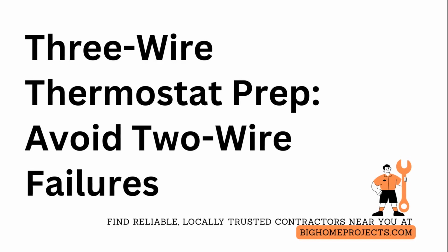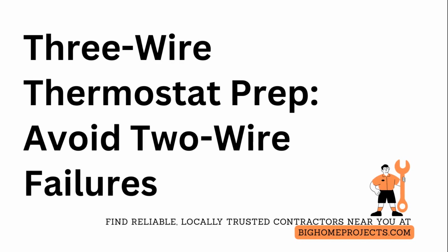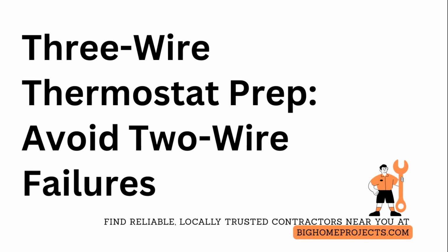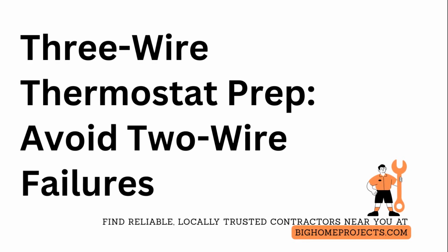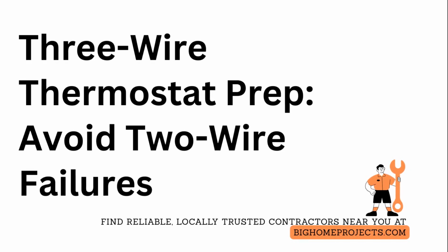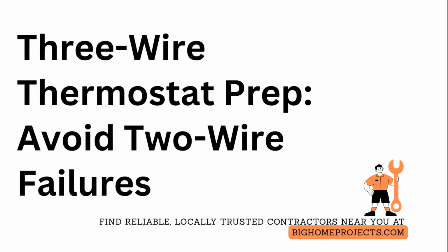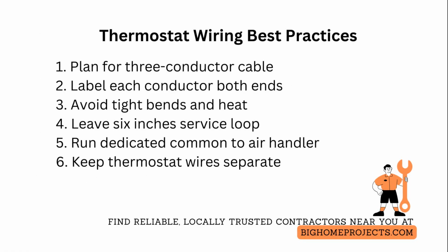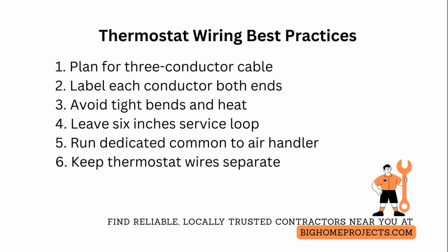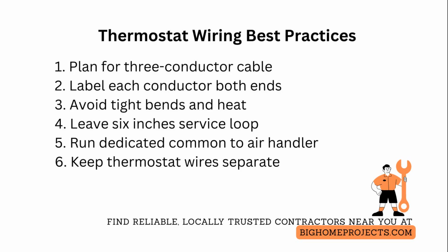Thermostat wiring and replacement. Always run one extra conductor than you think you need, so you're ready for 2-wire condensing units, smart thermostats, or future upgrades. When replacing or wiring a thermostat, plan for 3-conductor cable and label each conductor at both ends to avoid confusion during installation. Bring a continuity tester to verify wire integrity and mark the common wire for heat pump or 2-stage systems so the contractor can identify it without guesswork.